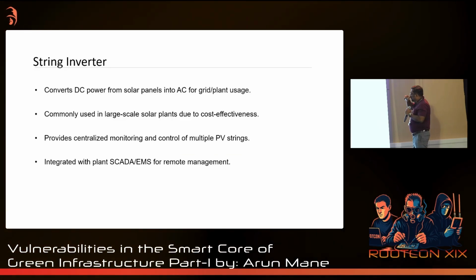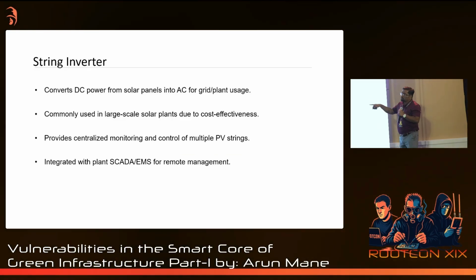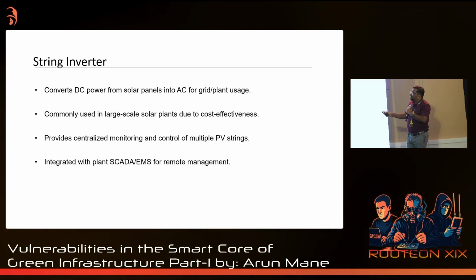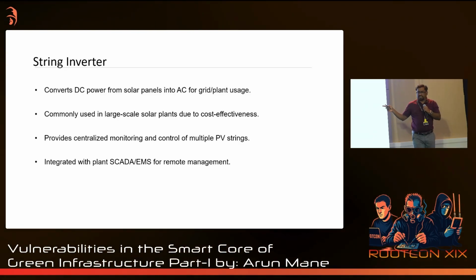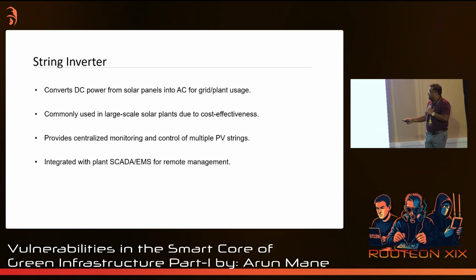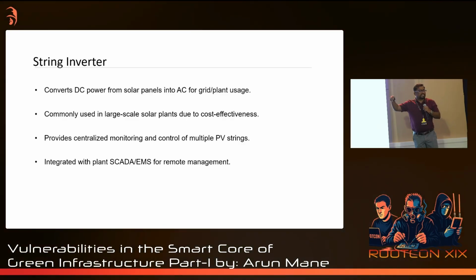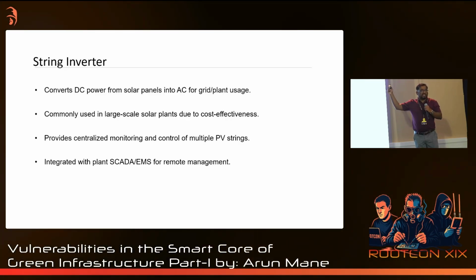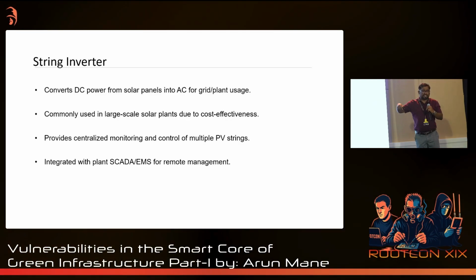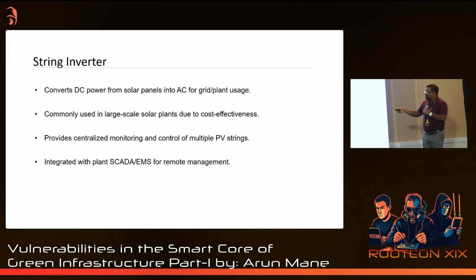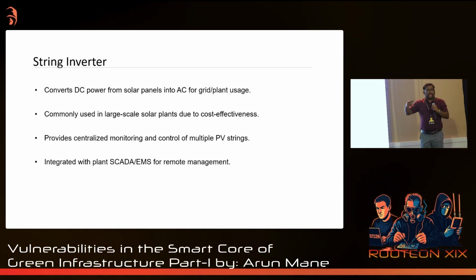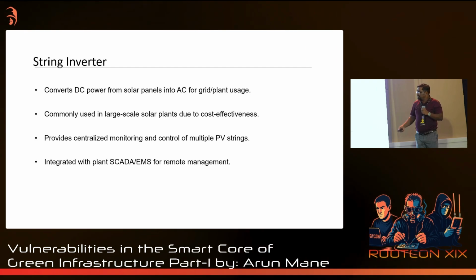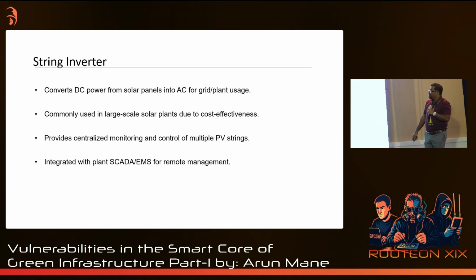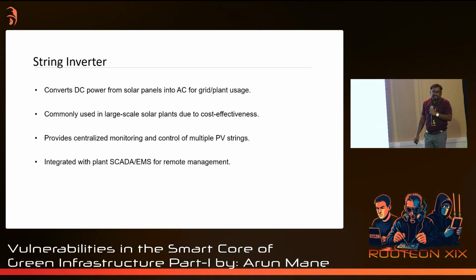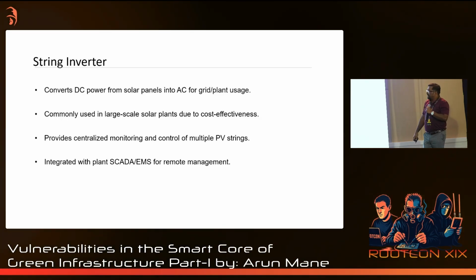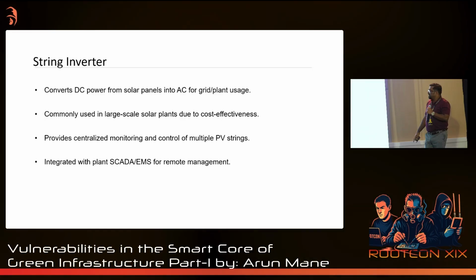So they convert DC power from the solar panel into AC for grid and plant usage - that's the work of the solar string inverter. It's commonly used in large scale solar plants due to cost effectiveness. A central inverter is very costly, while a string inverter is very cheap in comparison, which is why they use string inverters or micro string inverters. It provides centralized monitoring and control for multiple PV strings - PV meaning the solar panel - integrated with the plant SCADA system or EMS for remote management.